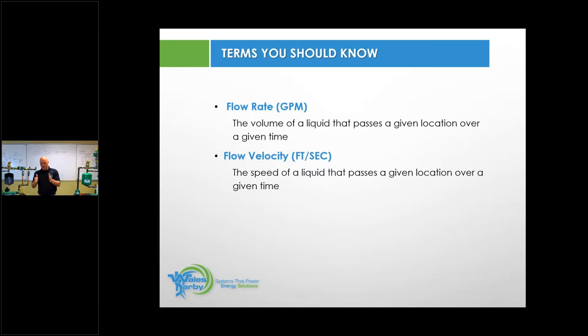If this is a gallon of water right here in a pipe, our goal is to move that every second, 2 to 4 feet from where it was originally. If we're under two feet per second, we don't have the ability to move little micro bubbles, air bubbles, in a system in a downward pipe. We're not going to be able to move them. So we want to have at least 2 feet per second of velocity, and our goal is to keep it somewhere between 2 and 4 feet.